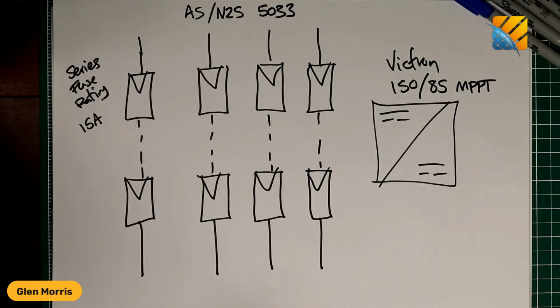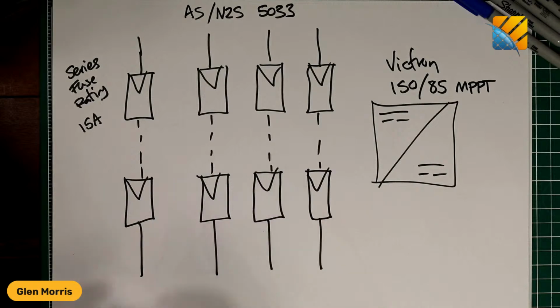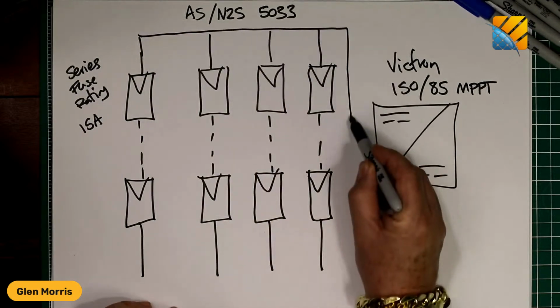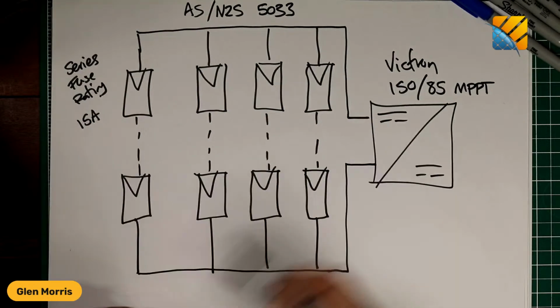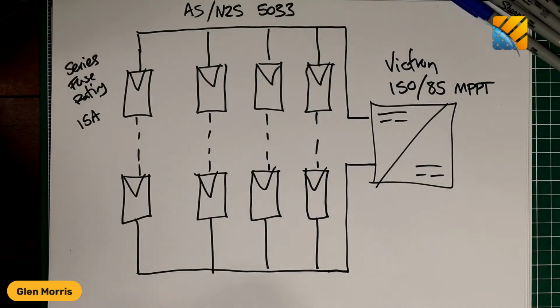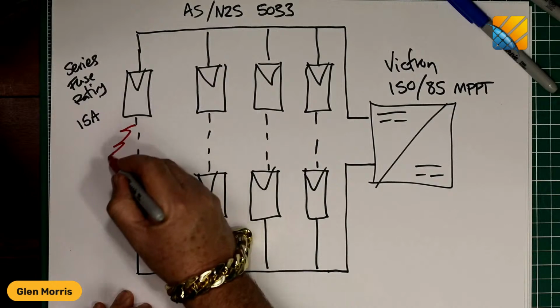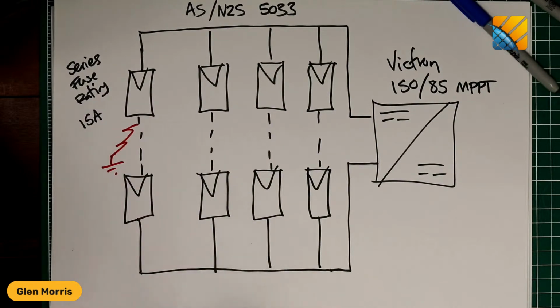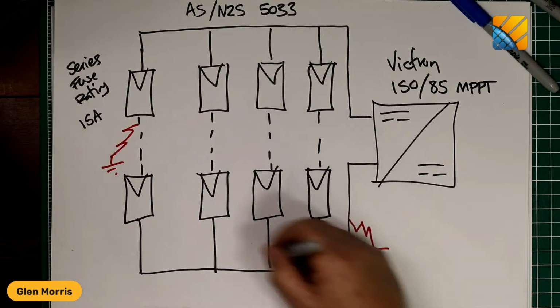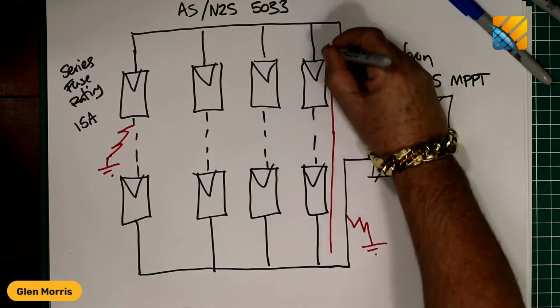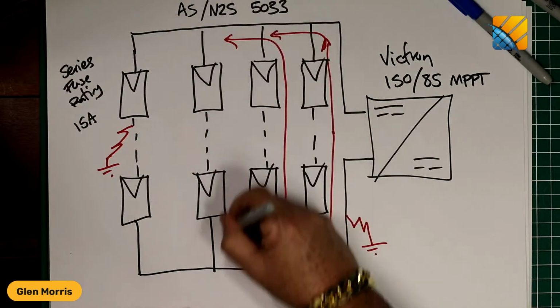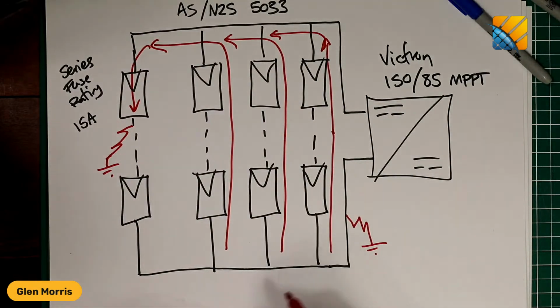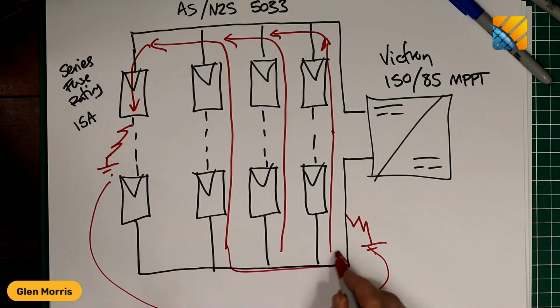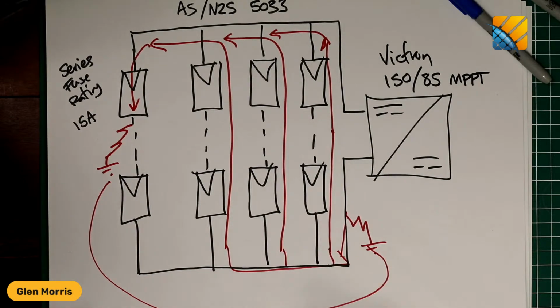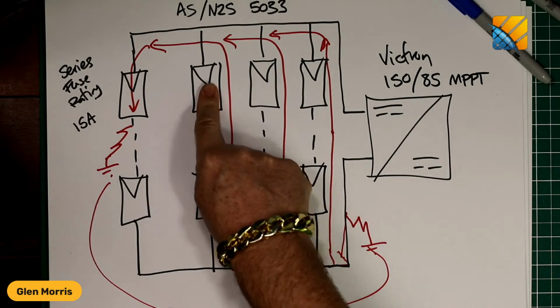So Craig, the issue you have is if you parallel those 4 strings and you have a fault in any one of them, so let's parallel them all up together. Because it's probably a floating array, meaning it doesn't have any reference to Earth, you actually need a couple of faults. So let's say a wire gets damaged on the roof and touches the conductive parts of the frame, and somewhere else in this system you have a similar fault. You now have a fault path that allows current to flow through, in this direction. So we've got 3 strings flowing in reverse into one string, and the loop path will be back through here.